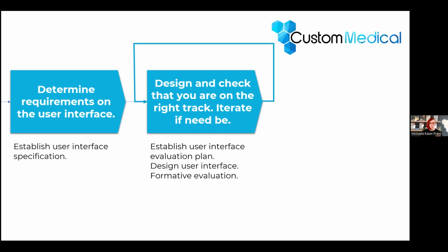If you're totally new and you're designing a totally new product, probably even one where there's no preceding device on the market or no predicate device in any version, I would guess that you at least need 3 to 5 iterations to make sure that you're on the right track. For an existing device or for just slight adaptations, you can even go with one or no formative evaluations at all.